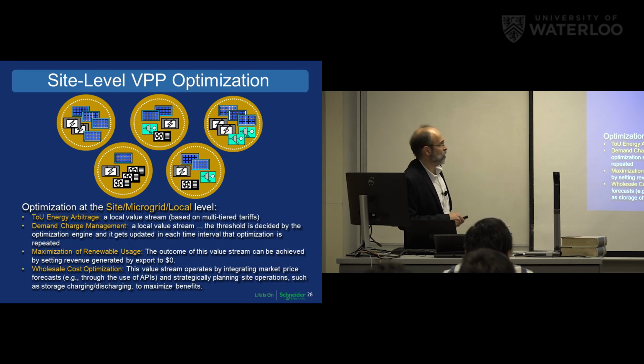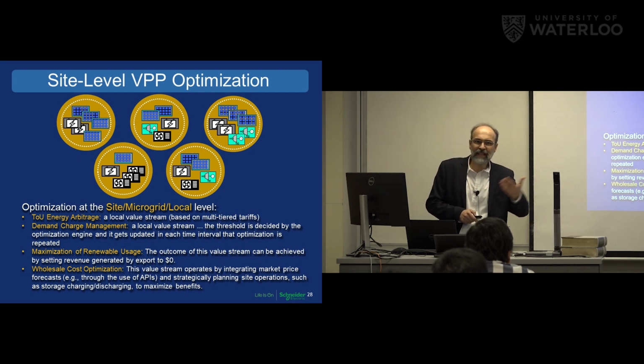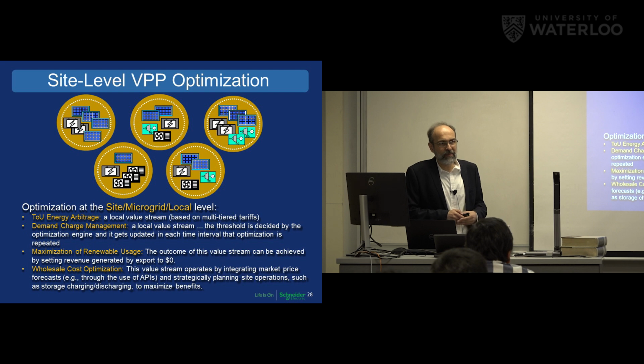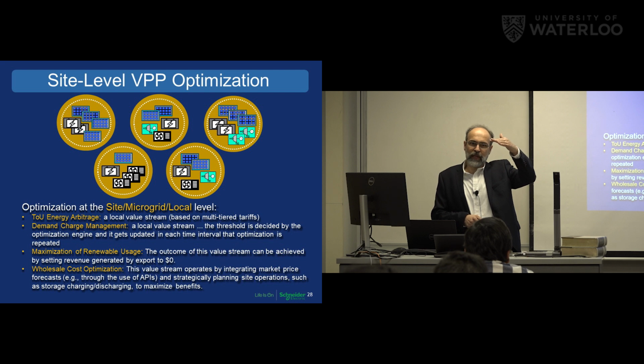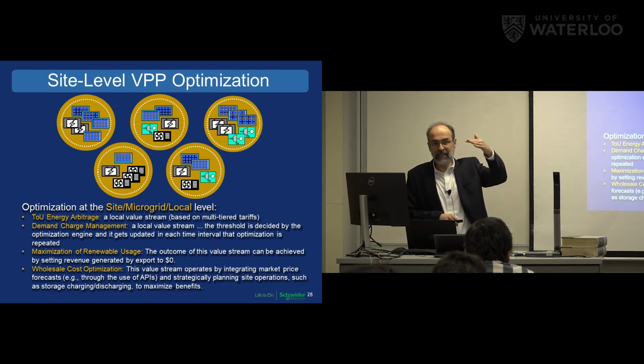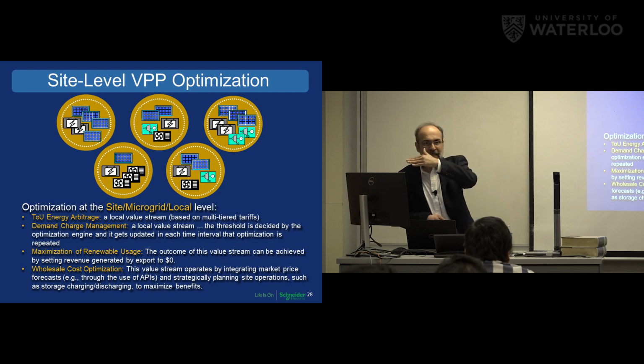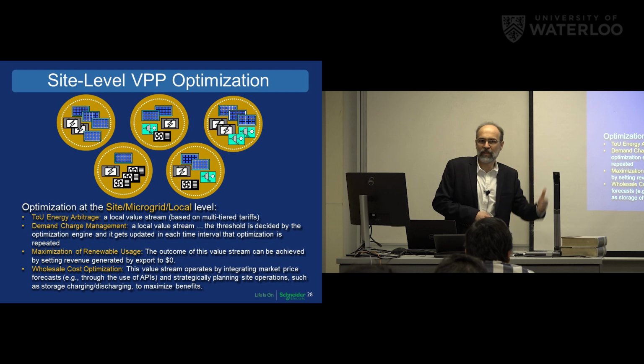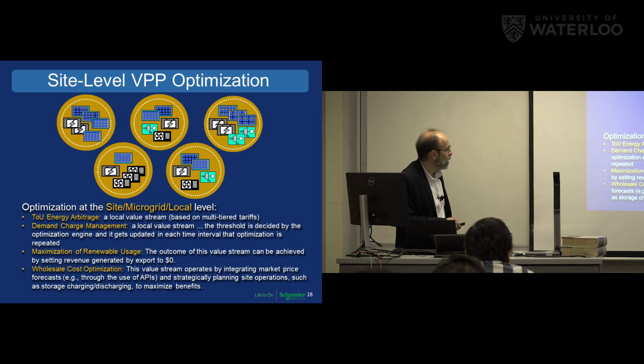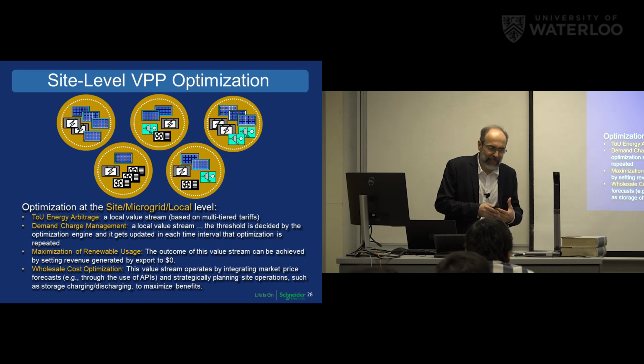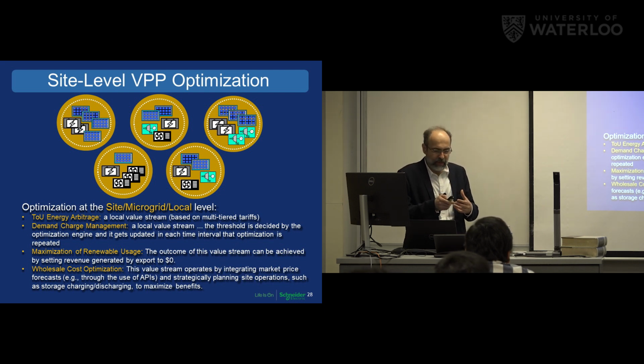For example, time of use energy arbitrage based on multi-tier tariffs, and demand charge management, which depends on different jurisdictions. Spain, Portugal, and the US have different demand charge management schemes, but in general you fix a certain kilowatt or megawatt limit not to cross, and offline you play with that, or that demand charge level is decided by the optimization engine, depending on the platform. And maximization of renewable usage isn't an independent value stream you can formulate directly, but indirectly we can achieve that.